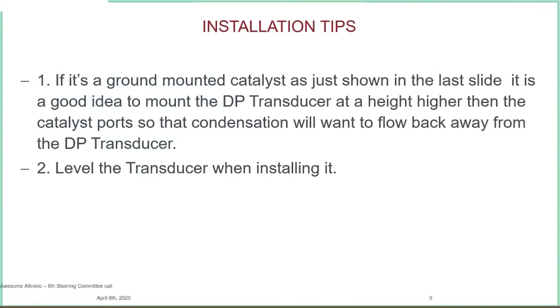If it's a ground mounted catalyst, as that one was very large in that last slide, it's a good idea to mount the DP transducer at a height higher than the catalyst ports, so that any condensation from the hot exhaust in the cold winters up here, we wanted to flow back any of that condensation or water back to the catalyst housing rather than into our DP transducer.